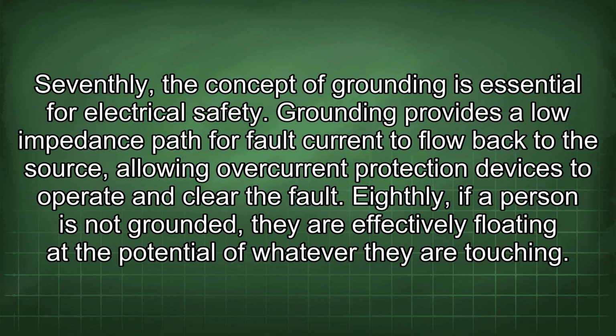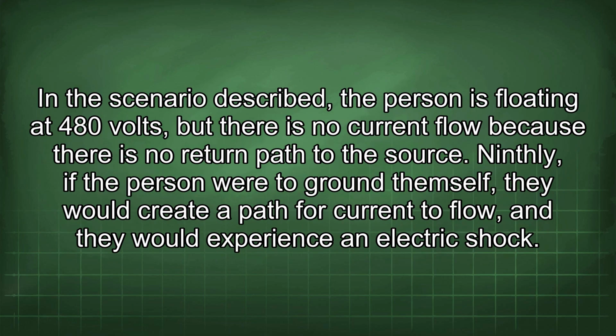Seventhly, the concept of grounding is essential for electrical safety. Grounding provides a low impedance path for fault current to flow back to the source, allowing overcurrent protection devices to operate and clear the fault. Eighthly, if a person is not grounded, they are effectively floating at the potential of whatever they are touching. In the scenario described, the person is floating at 480 volts, but there is no current flow because there is no return path to the source.